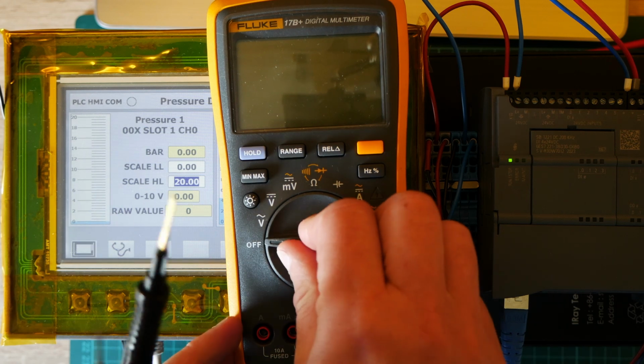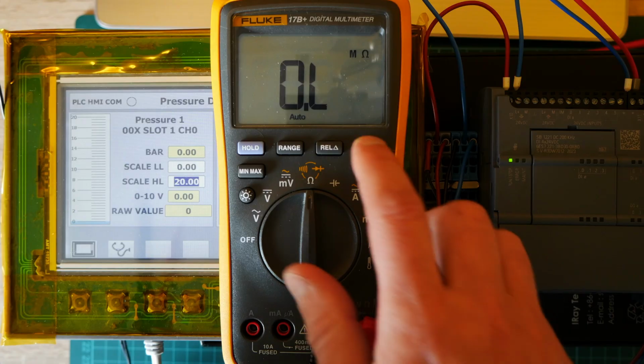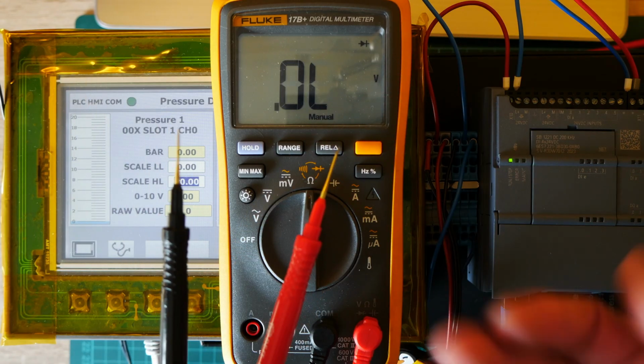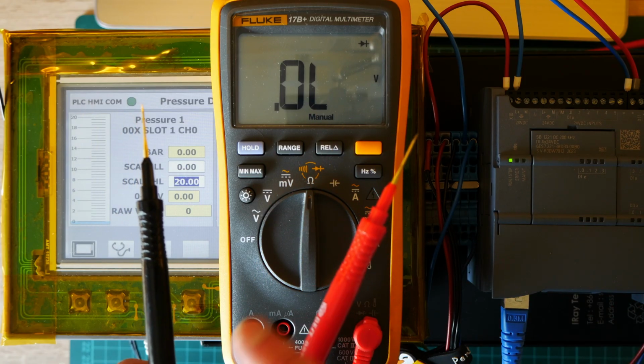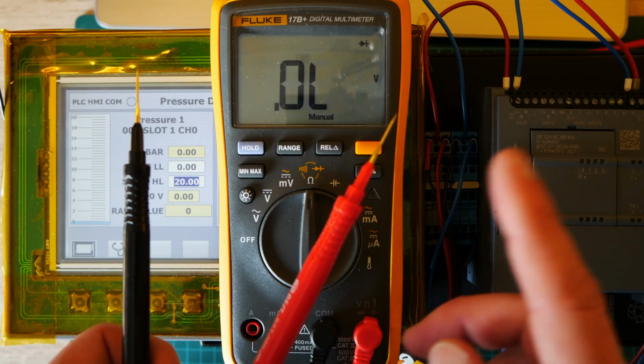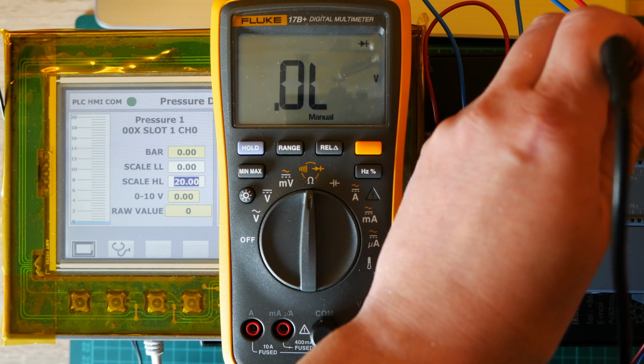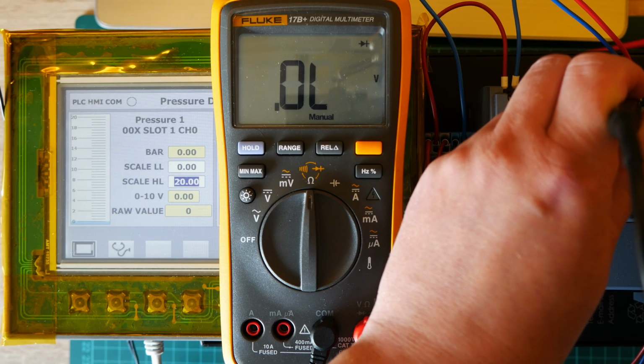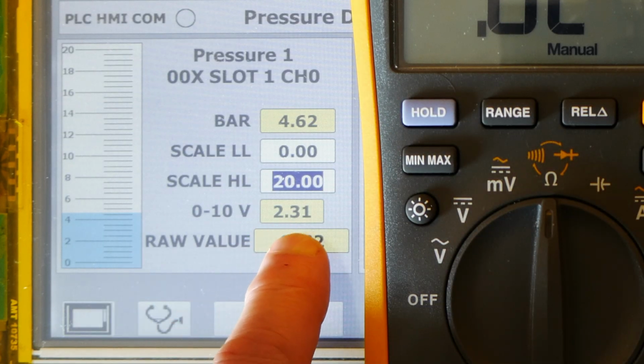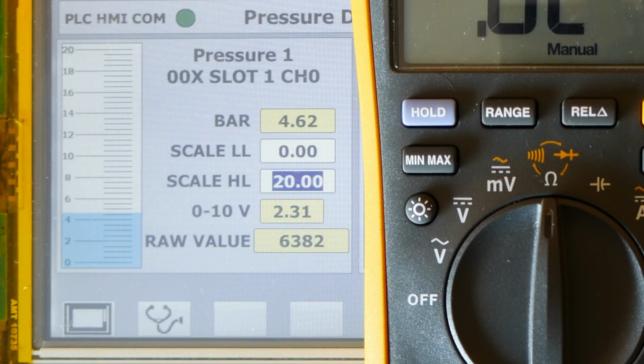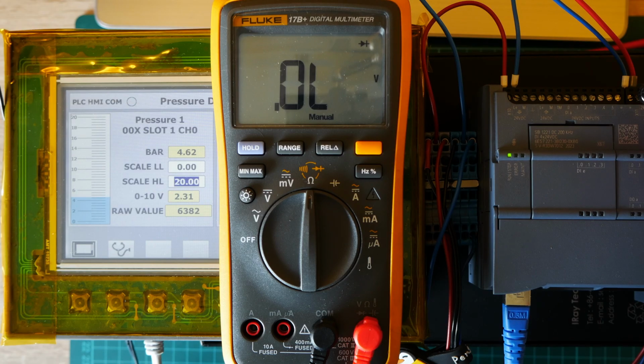Okay, so if we put our multimeter in diode mode, right now we have a source of voltage. This Fluke multimeter provides around 2.3 volts DC. So if I connect the negative probe to the negative analog input contact and the positive probe to analog input channel 0, I see on my HMI that I am providing 2.3 volts, and it shows a reading. So this reading is correct. This is just a sanity check, okay? This is working or it's completely dead.